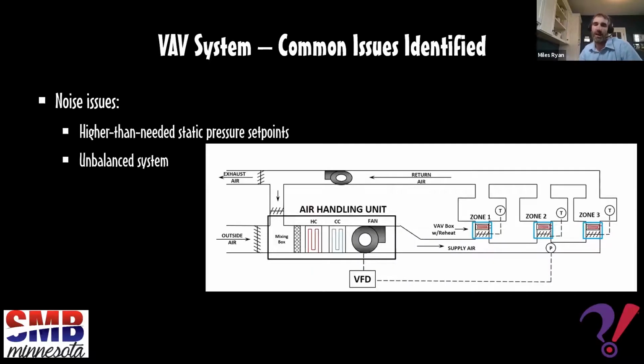Some more issues. Oftentimes the static pressure set point, that right here that the fan is controlling to, is way too high. And if it's way too high, you might have all of the dampers in the VAV boxes pinched down way too much, and that might create some noise further down into the occupied space. Or you might have, within a particular zone, an unbalanced system where all of the air is coming out of one of the diffusers and the other three have negligible amounts coming out of them. And in that case, that diffuser could rattle. It might be pushing higher airflow than desired, and it could create some noise issues.